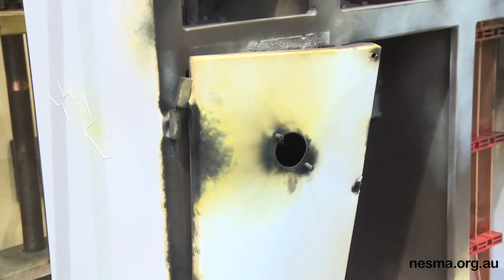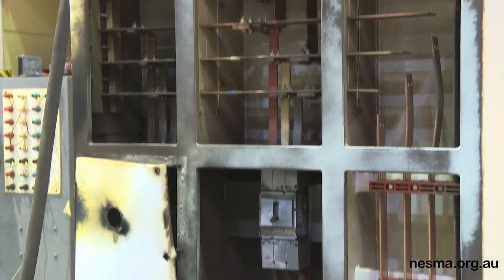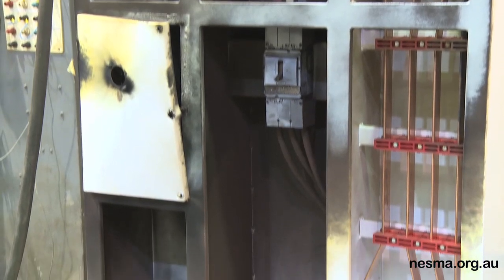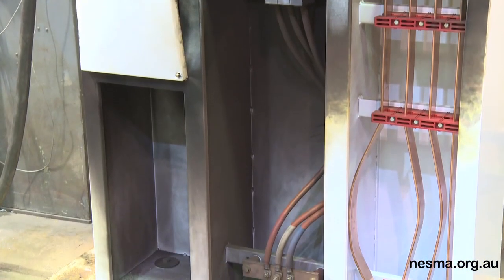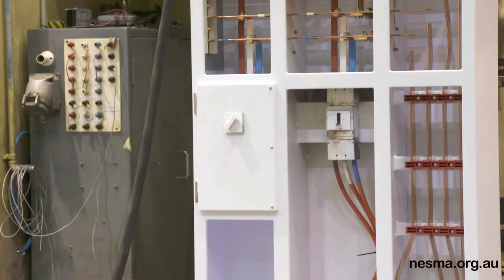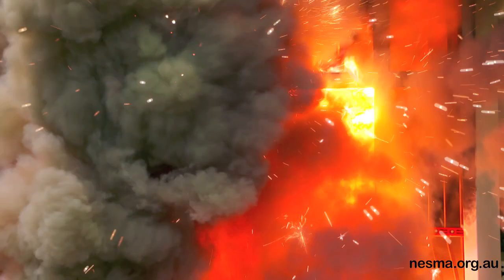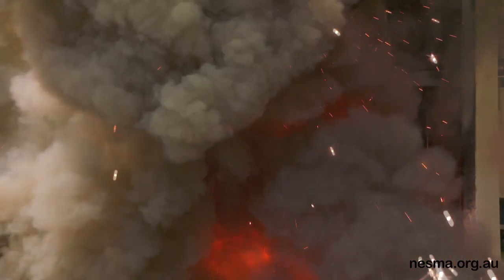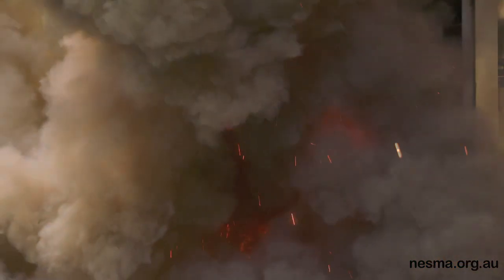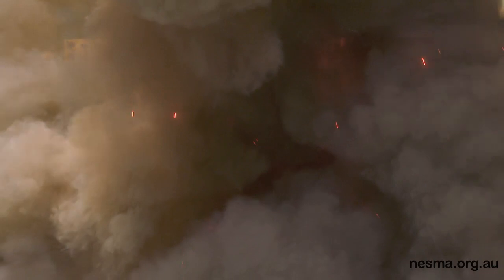The assessment of the test: now normally if we're carrying out a test to Appendix ZD, there would be that indicator cloth, either the white if we're using the Australian ZD version, or the black squares, which is the IEC arrangement to 61641, spaced in front of the assembly. For the white cotton gauze, it would be 250 millimetres from the front of the assembly, and for the black IEC indicator cloth would be 300 millimetres from the front of the assembly.